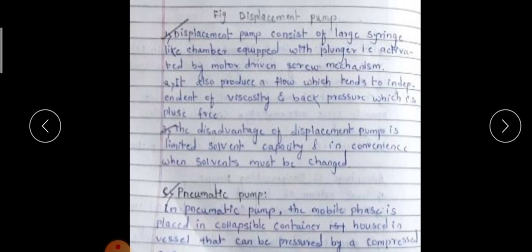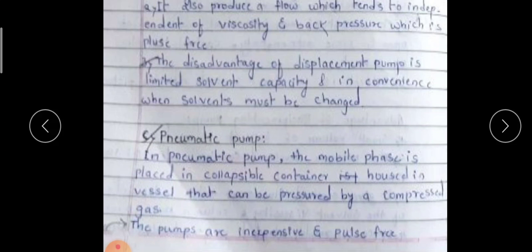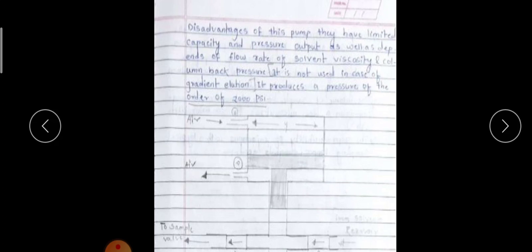In the pneumatic pump, the mobile phase is placed in a collapsible container housed in a vessel that can be pressurized by a compressed gas. These pumps are inexpensive and pulse-free. The disadvantages are limited capacity and pressure output, flow rate depends on solvent viscosity and column back pressure, it is not used for gradient elution, and it produces a pressure of only about 2000 psi.